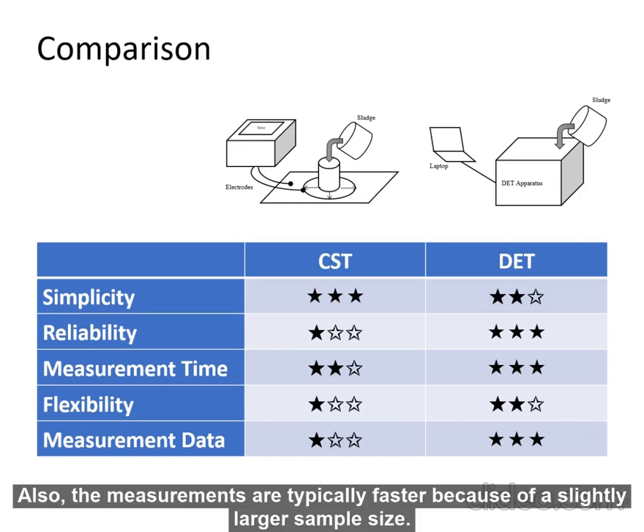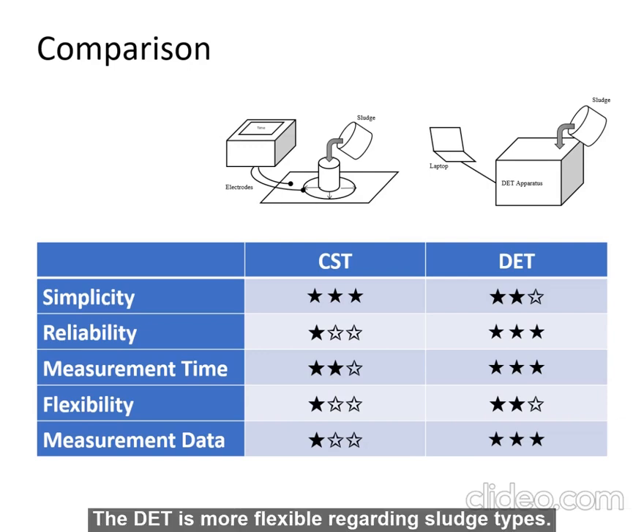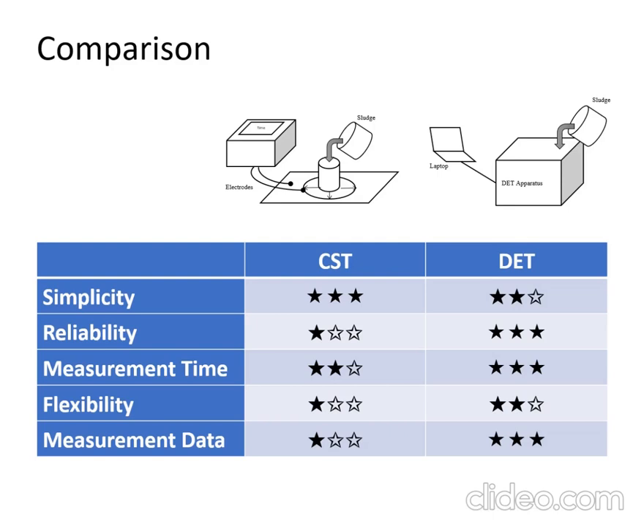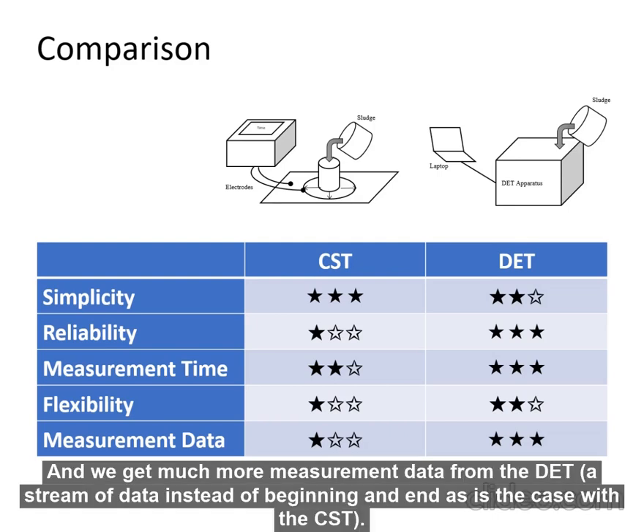The measurements are typically faster because of a slightly larger sample size. The DET is also more flexible regarding sludge types. And we get much more measurement data from the DET — there is, so to speak, a stream of data instead of just a beginning and end, as is the case with the CST.